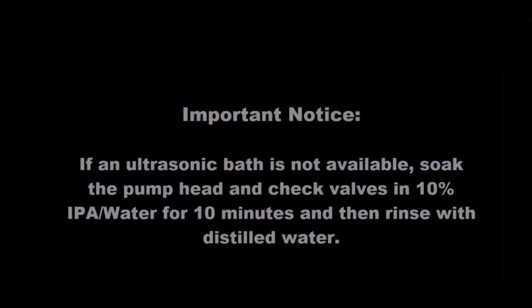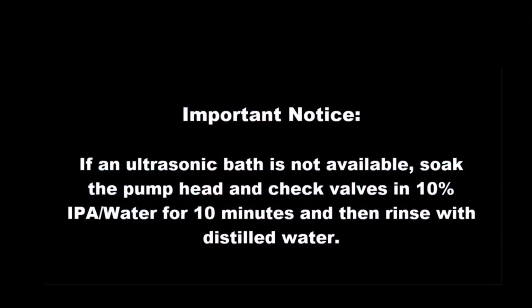If an ultrasonic bath is not available, soak the pump head and the check valves in 10% isopropanol water for 10 minutes and then rinse with distilled water.